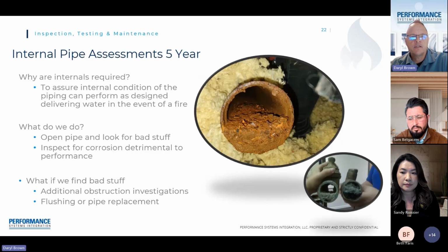Next items you see here, this is some of our internal pipe inspections that we do during the 5-year. These are actually pictures of pipes we've pulled. You can see on that top picture that half the circumference of that pipe is actually corroded and clogged. So not only is that going to be pushed into sprinkler heads and clog them, but it's also going to prevent the required amount of water to flow through the system. So we need to verify that it is clear of debris, clear of corrosion, and if not, come up with a remediation plan. Sometimes it's actually replacing a section of piping. Sometimes it's just flushing.